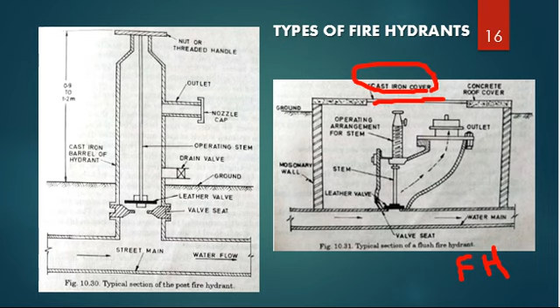Just to make the flush fire hydrants more easily recognizable, you can attach a plate bearing the letters F and H. F stands for fire, H stands for hydrant. So FH, you can attach a board written FH on it, or on some nearby building or any object, so that you can easily come to know that there is a fire hydrant nearby. And it can also be inscribed on the cover of the fire hydrant. There is a cast iron cover, you can see here. On the cover also the letters F and H can be inscribed, so that anyone who sees it will come to know that there is a fire hydrant inside the chamber, right?